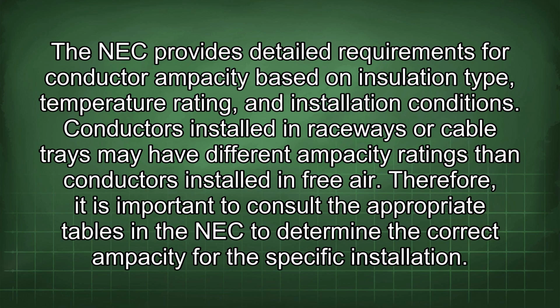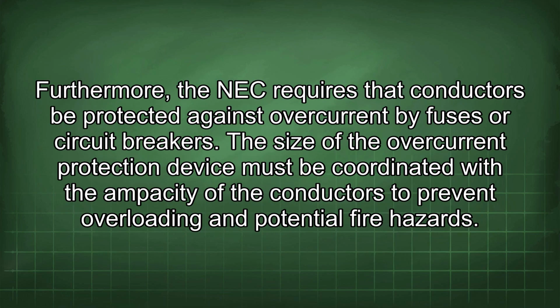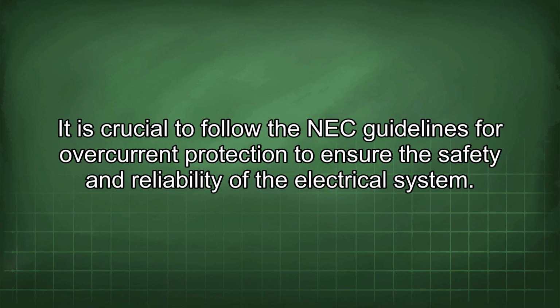Conductors installed in raceways or cable trays may have different ampacity ratings than conductors installed in free air. Therefore, it is important to consult the appropriate tables in the NEC to determine the correct ampacity for the specific installation. Furthermore, the NEC requires that conductors be protected against overcurrent by fuses or circuit breakers. The size of the overcurrent protection device must be coordinated with the ampacity of the conductors to prevent overloading and potential fire hazards. It is crucial to follow the NEC guidelines for overcurrent protection to ensure the safety and reliability of the electrical system.